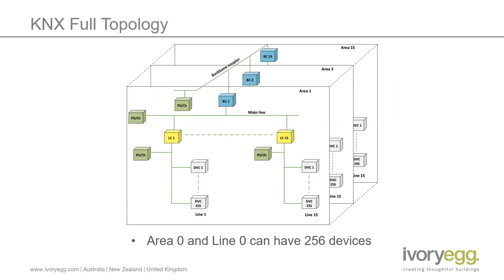Another aspect this changes is the number of devices on line zero and area zero. Previously, this was limited to 64 devices as you weren't able to have line repeaters on these system lines, but that restriction has been removed. You can now have 256 devices on these lines, which increases the total number of devices possible in a KNX installation to 61,696.